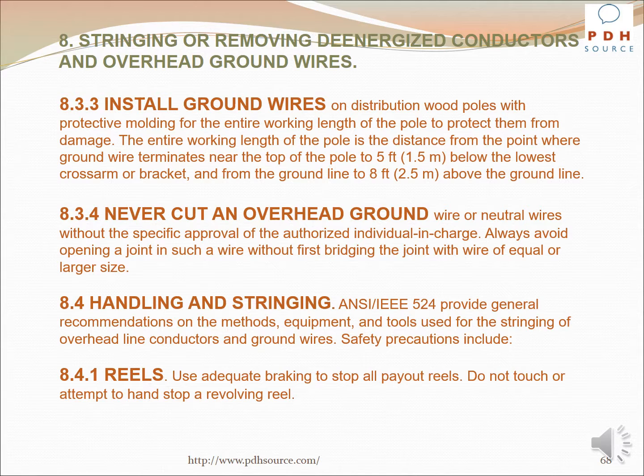Never cut an overhead ground wire or neutral wires without the specific approval of the authorized individual in charge. Always avoid opening a joint in such a wire without first bridging the joint with wire of equal or larger size. ANSI IEEE 524 provides general recommendations on the methods, equipment, and tools used for the stringing of overhead line conductors and ground wires. Safety precautions include reels.